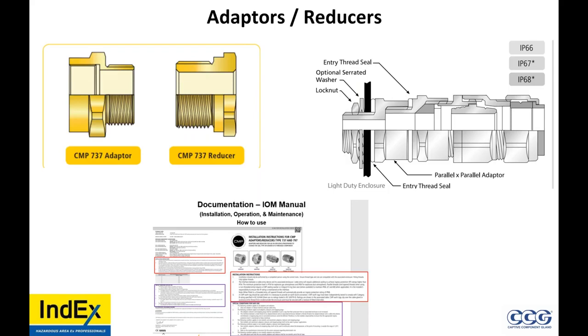If something's easy, cool. So the manufacturer calls for the use of 2 entry thread seals, 2 IP washers, one that side and one that side of the reducer or adapter. So on this side and this side. And if you read down in the details, it says all that, and on the certificate. Now, it tells you you have to measure the roughness of the surface of the device. If it's too rough, you have to use an IP washer. Do any technicians go out in the field with a micrometer, or do you just install the IP washer? Probably best just to install the IP washer, you would think.